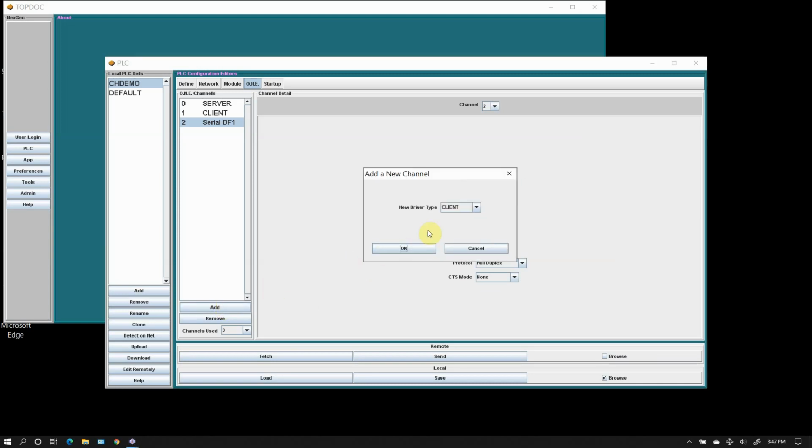And the third type of channel I can add is Data Highway Plus. The KTX is for systems that have an obsolete KTX card installed. That would be the 1784 Allen Bradley PKTX or KTX card. The SST DH Plus, this would be the 5136 SD, again, an obsolete product. And the Smart Data Highway Plus is the internal Data Highway Plus interface in the Smart SoftPLC.